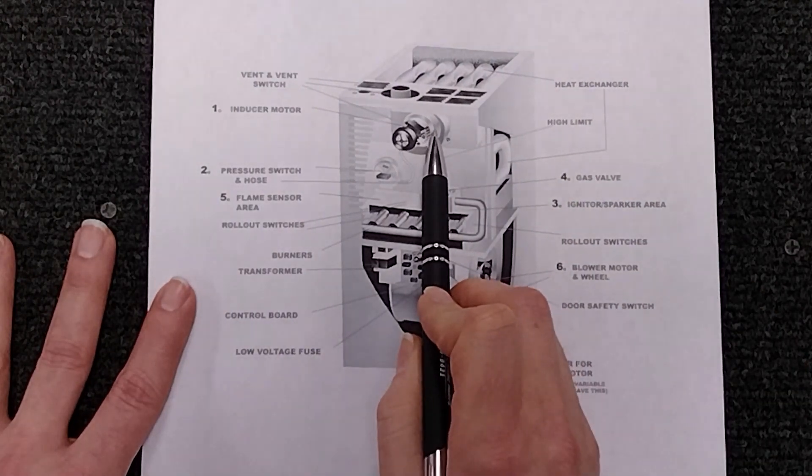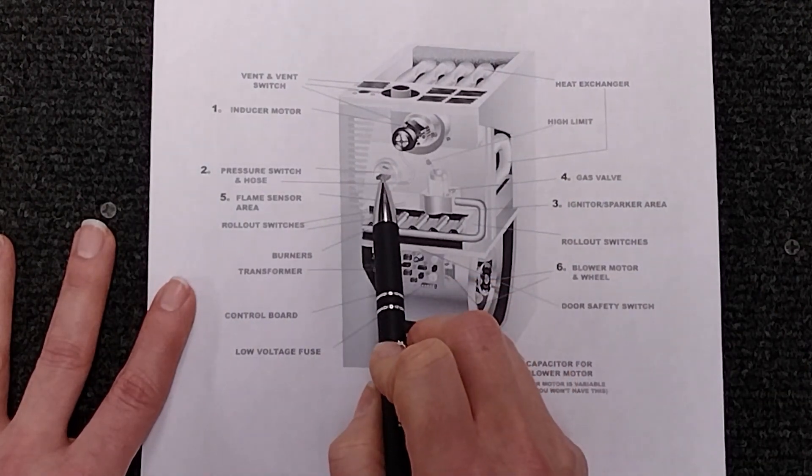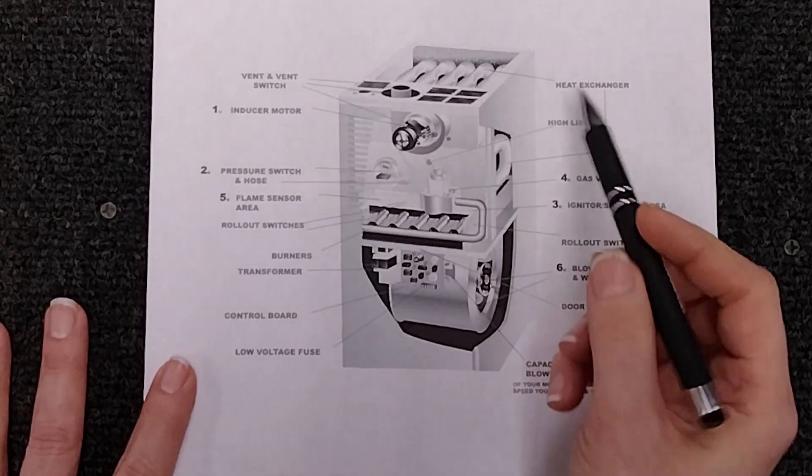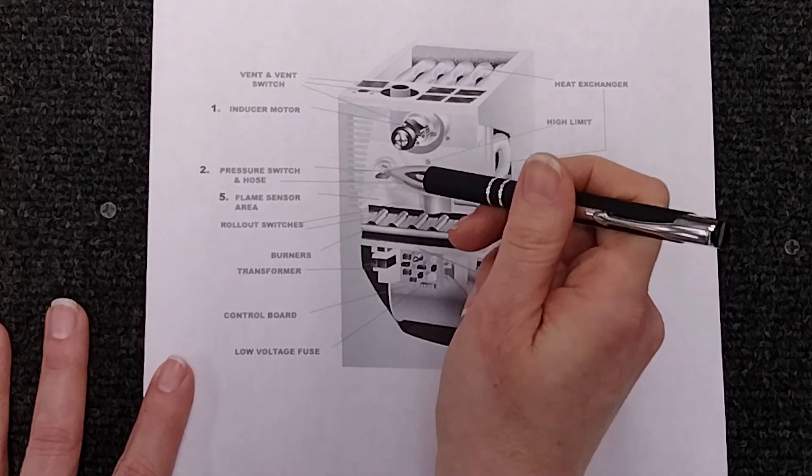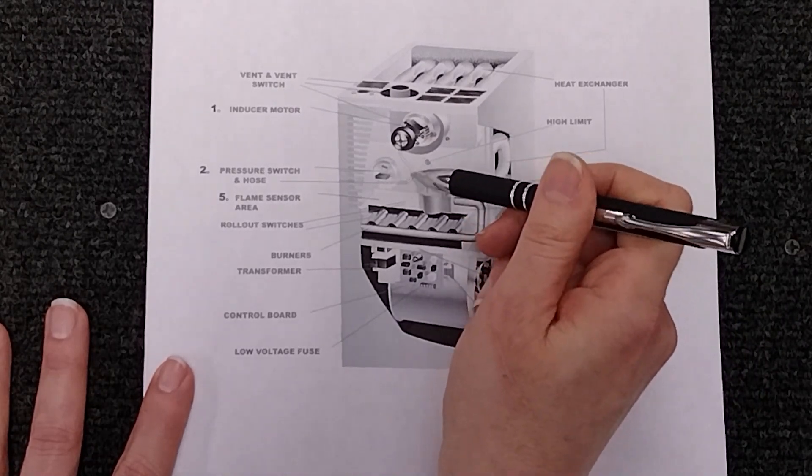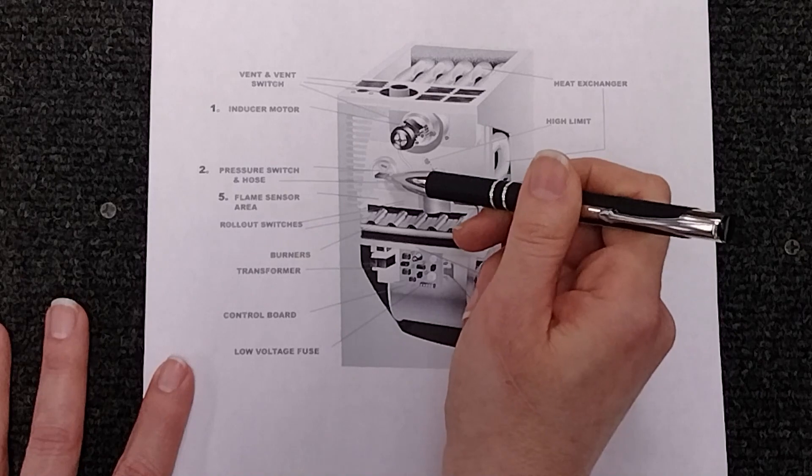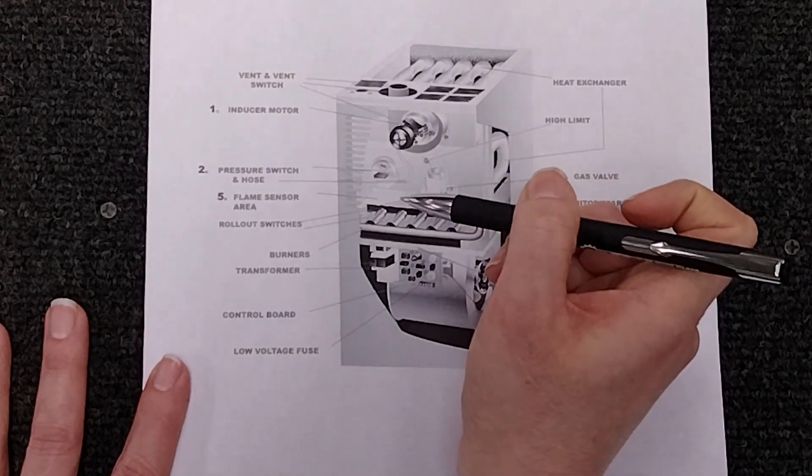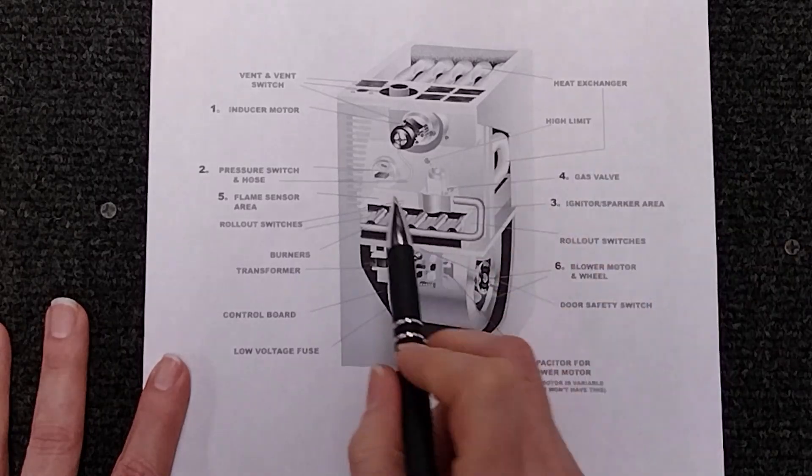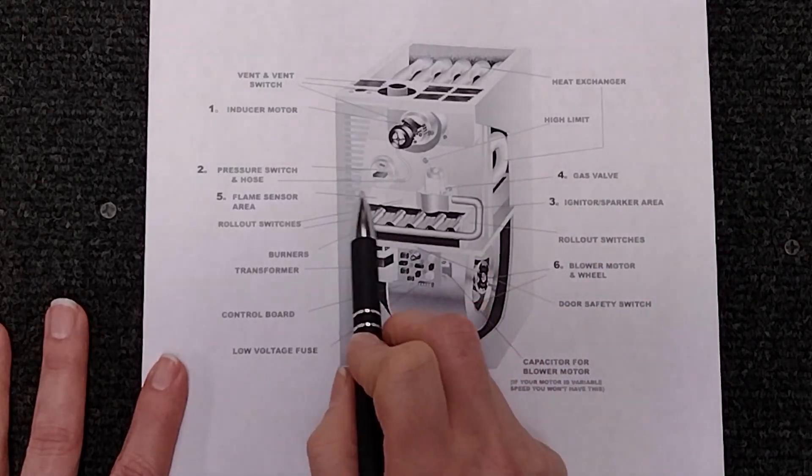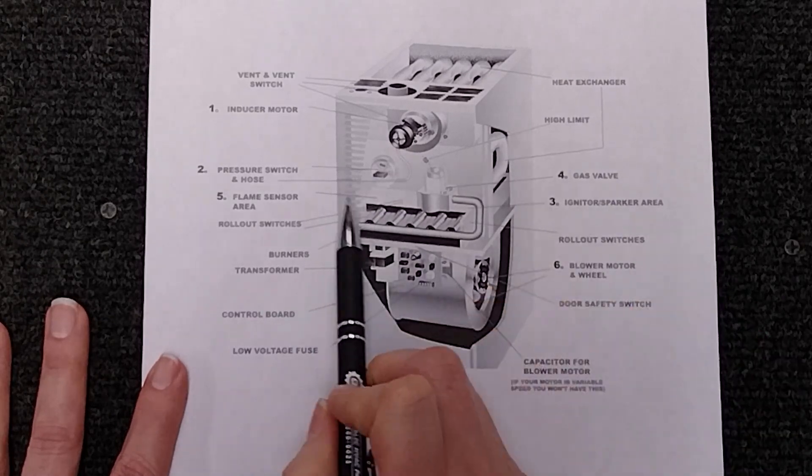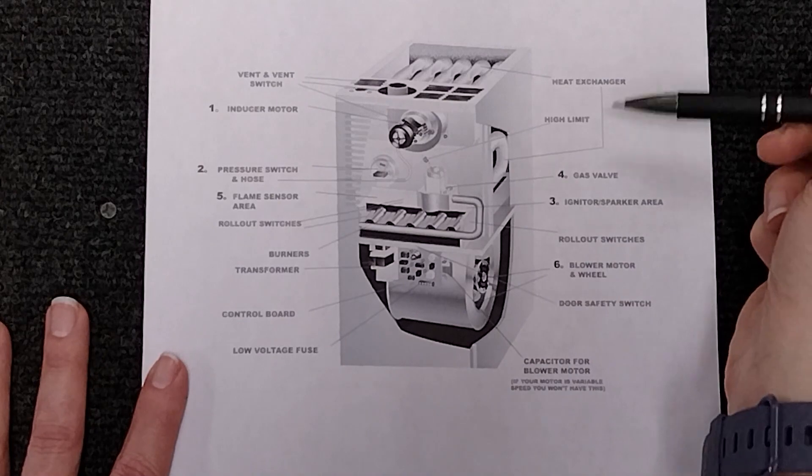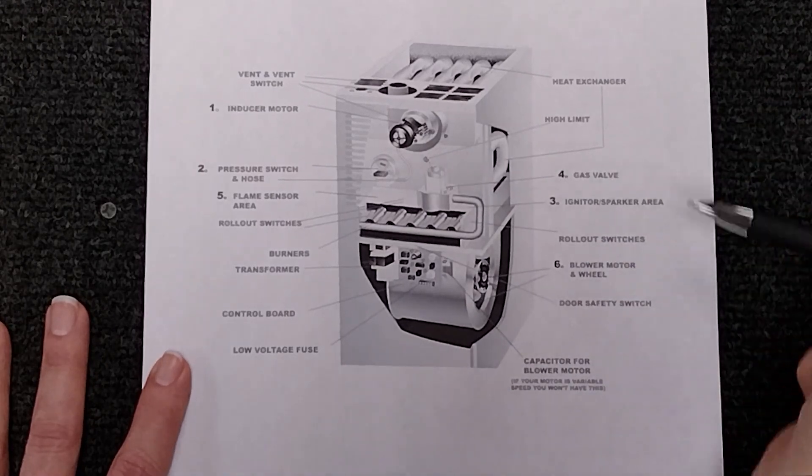Once that comes on your pressure switch in most cases are going to be under negative pressure. So when this comes on it's going to pull that negative pressure through this tube and it's going to close the line that's going through the pressure switch. Once that pulls through obviously path of least resistance that low voltage is going to go through that line and it's going to go through a series of switches.